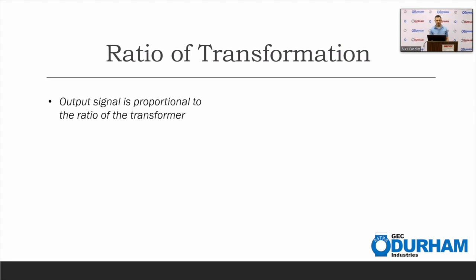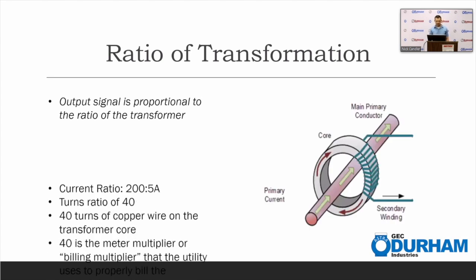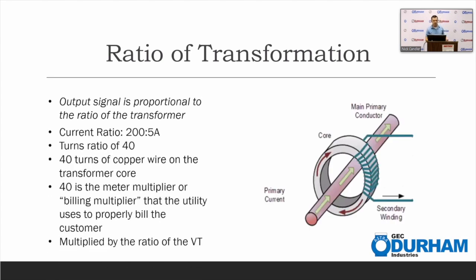It's important here to talk about the ratio of transformation. There's a couple terms that we use to describe what's going on here. We have a current ratio, or we refer to that as the nameplate ratio. This is a 200 to 5 amps, for example. We also have a turns ratio. In this case, 200 divided by 5 would be 40. And coincidentally, that's going to include 40 turns of copper wire on that current transformer.